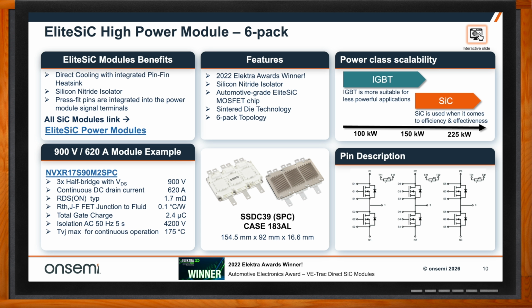This module can incorporate IGBT technology or SiC, silicon carbide technology, depending on the power rating. As you go higher with the power, you need less losses, and silicon carbide as a technology can switch higher but also have lower losses. This makes it a better technology for higher power ratings.